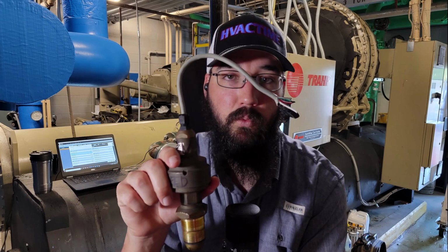And that's part of what we're testing for when we do a calibration test: how does the valve move? How does it sound when it moves? So this is where using your sight glass and your listening come into play. And having a mechanical failure like this is one of the more common failures that I personally have dealt with. There are electrical failures, and we'll look at that. This one in my hand failed electrically, but mechanical is the main failure that I personally have dealt with.